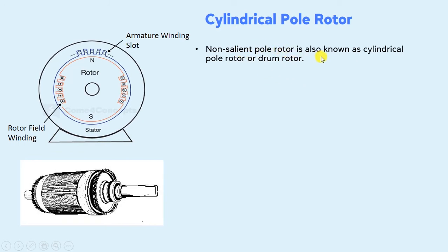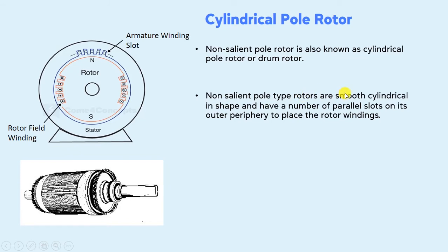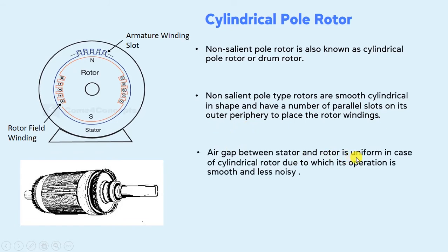Now moving on to the next part, which is the cylindrical pole rotor. Non-salient pole rotor is also known as cylindrical pole rotor or drum rotor. Non-salient pole type rotors are smooth and cylindrical in shape, and have a number of parallel slots on their outer periphery to house the rotor windings. Here you can see in the cross-sectional view of the cylindrical pole rotor — it is cylindrical in shape and these are the parallel slots on the outer periphery in which the rotor windings are placed. The air gap between the stator and rotor is uniform in the case of a cylindrical rotor, and you can also see that the air gap is uniform.